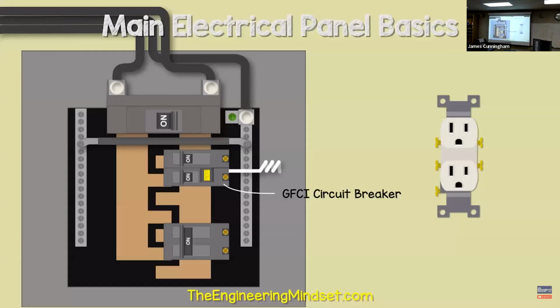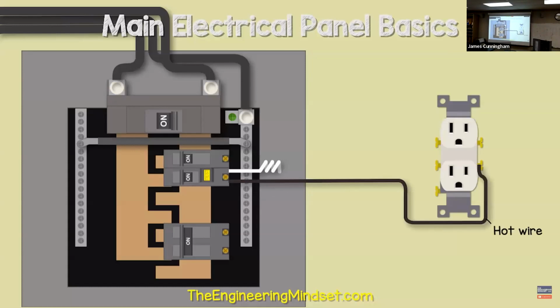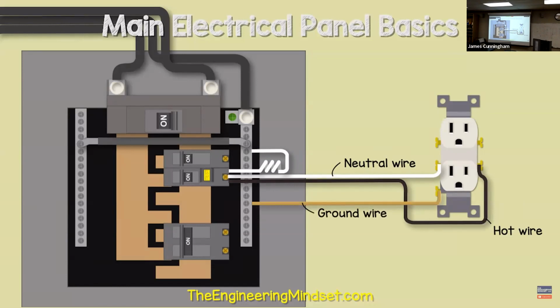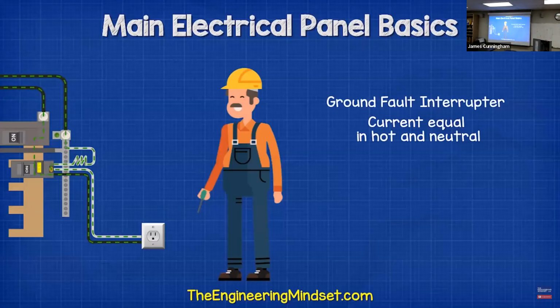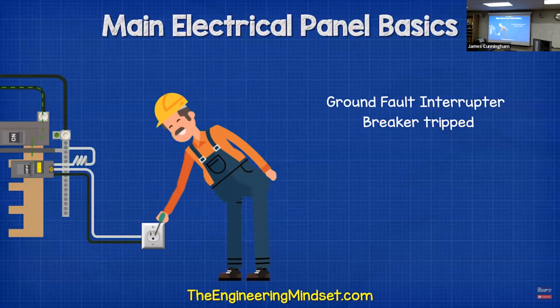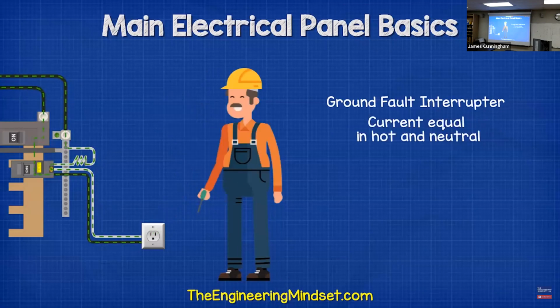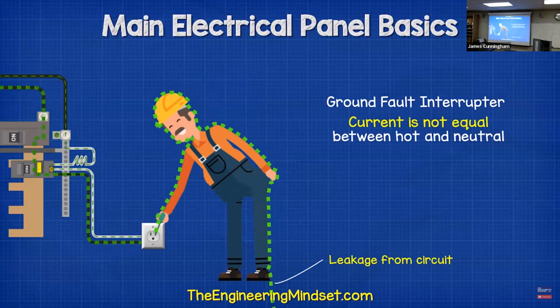If we took a standard outlet, we would take our hot wire from the breaker and connect this to the outlet terminal. Then we take the neutral wire and run this back directly to the circuit breaker to a specific neutral terminal. We then connect the pigtail wire into the neutral bus bar. This will provide the return path. And of course, we run the ground wire from the outlet back to the neutral ground bar. If we look at this example, the current is flowing normally until the guy sticks a screwdriver into the socket. The electricity then flows through him instead of the neutral wire. The GFCI is measuring the current in the 2 wires and notices that these are not equal. It then automatically trips the breaker to cut the power and save the man's life.